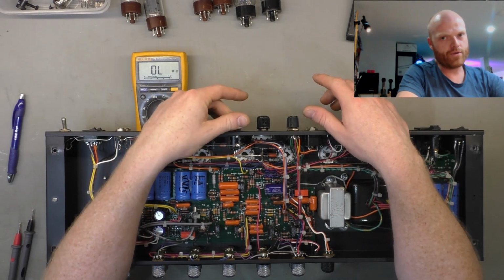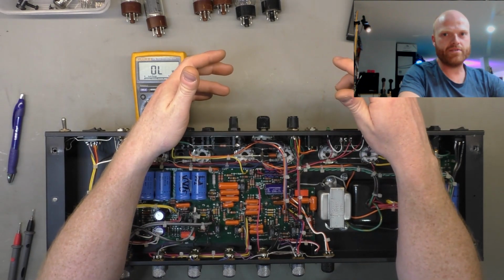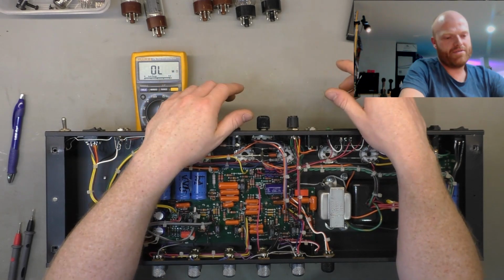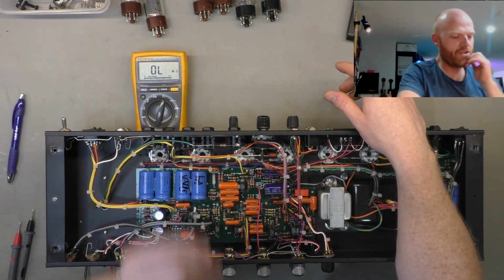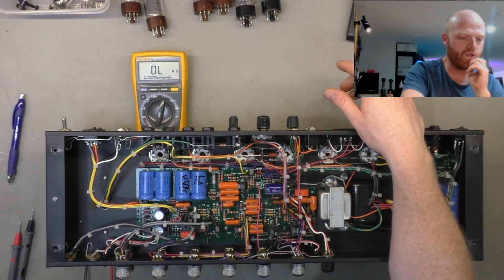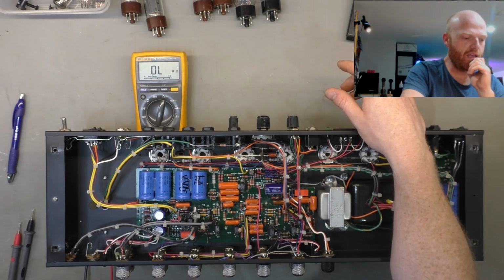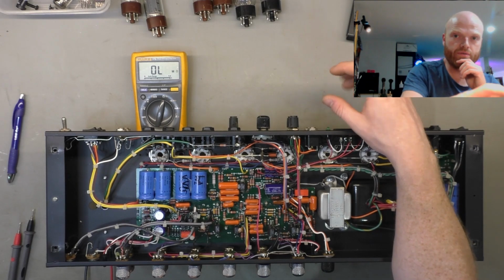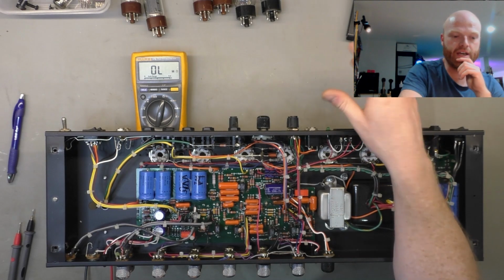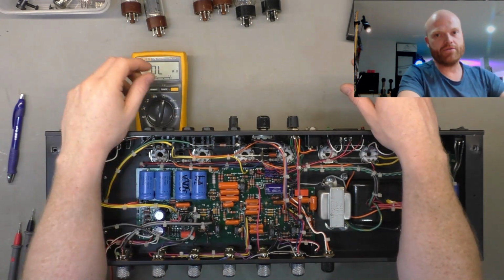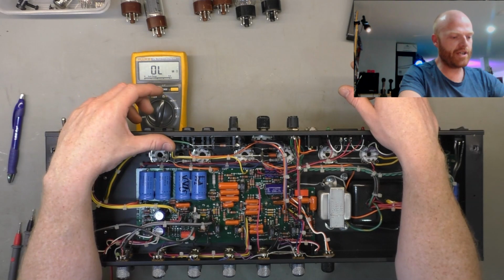I see that a lot on forums - one side's 20 ohms, the other side's 30 ohms. It's fine, as long as you don't have anything open circuit or any shorted windings, which would load it down significantly. Or a short to the actual casing, the laminations of the transformer, because that would give a dead short to ground.